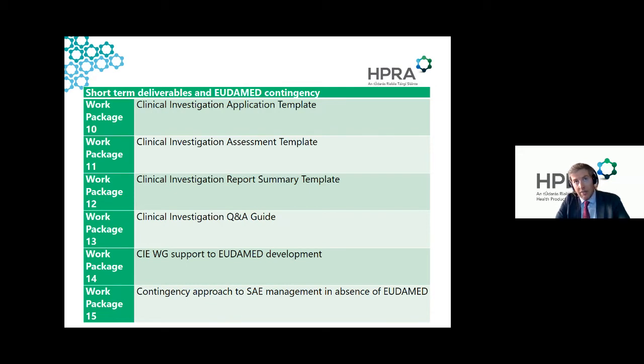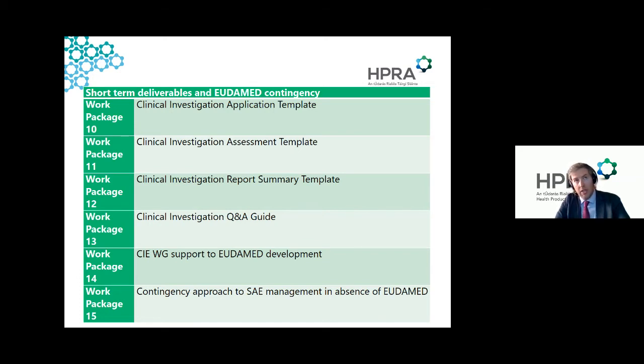Work package 12 concerns a clinical investigation report summary template. Those aware of clinical investigation report requirements in MDR will know that the clinical investigation report and the summary need to be publicly available. Annex D of the newly revised ISO 14155 has lots of detail about the full report. We're looking to provide guidance for the summary report, since it needs to be understandable to the user of the device — which in some cases will be a lay person — so there is some policy work to do.